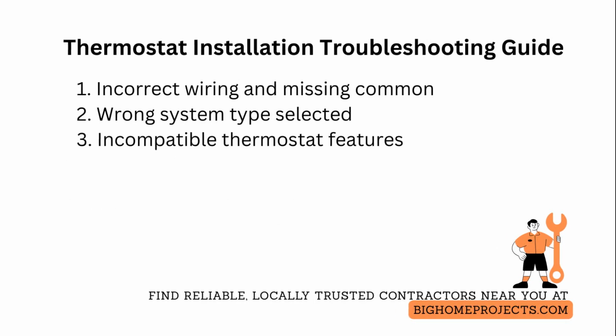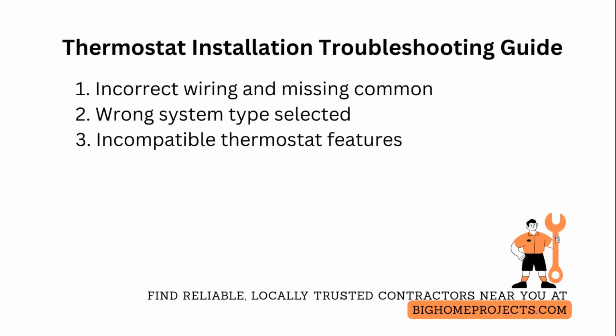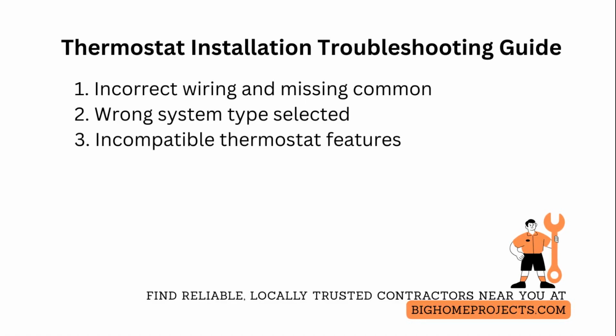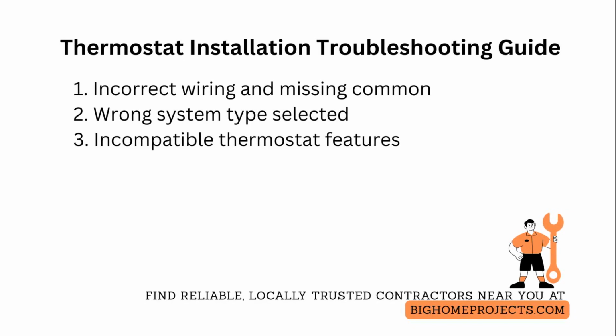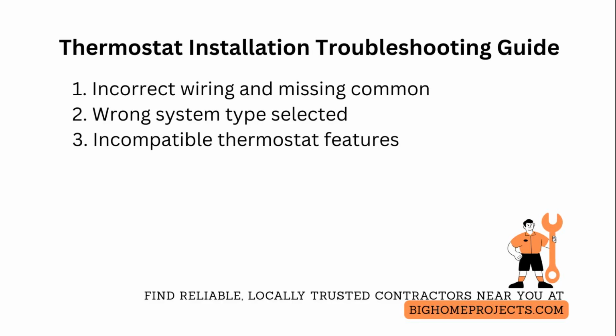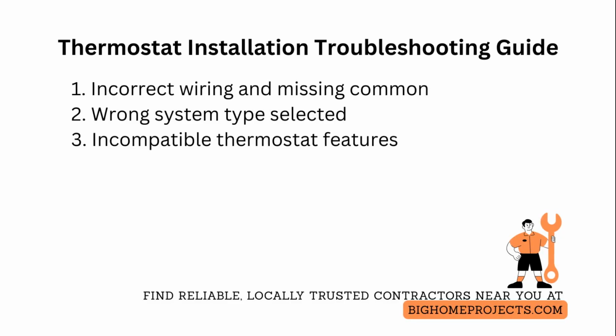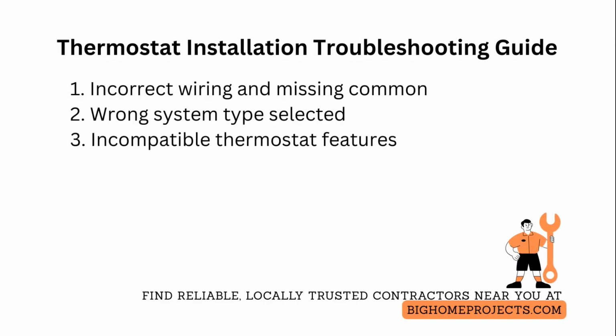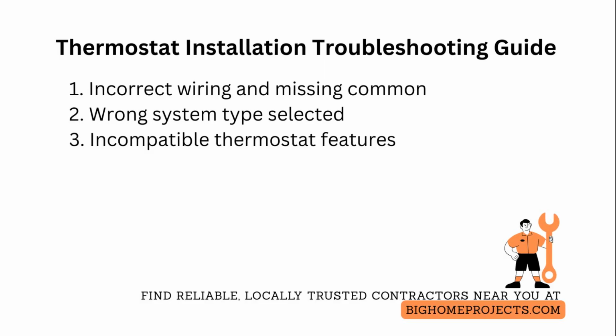One of the biggest problems is incorrect wiring labeled as common wire issues, causing limited power or loss of Wi-Fi. Fix by locating the actual common at the air handler using a power extender kit, or installing a dedicated 24-volt transformer and retesting voltage.